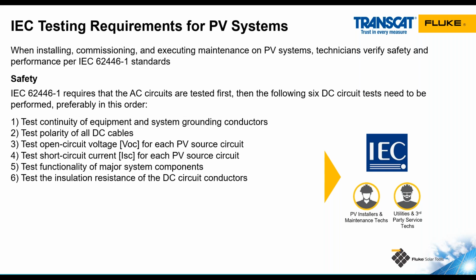Category 1 are safety tests. This includes testing the continuity of the equipment grounding conductors and the grounding between the non-current carrying metal parts. So making sure our module frames are bonded to the racking, it's bonded to the equipment ground, things like that. We're going to test the polarity, open circuit voltage, and short circuit current of our PV circuits. We'll test our equipment functionality, make sure our disconnects work, our overcurrent protection devices are functional, make sure the inverters are working properly. And finally, we'll do insulation resistance testing of all the DC circuits to make sure that the insulation was not compromised during the installation process.